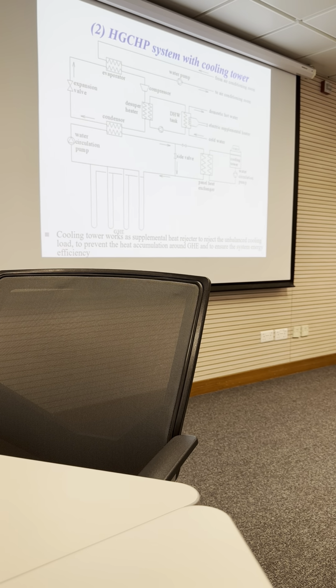Because you see, with a cooling tower, the COP is much higher. Then, can we use a cooling tower for this coupled heat pump system in a short time period? For example, in July and August, only from noon to afternoon, when we have peak cooling load. It means we want to combine our ground boreholes and the cooling tower. We only use the cooling tower to reject some energy to the air by evaporation, for limited time. Most of the time in the year we don't use it. In this way, we can solve the problem partially.